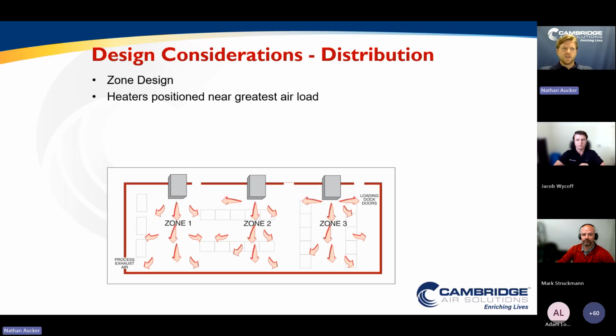So we're looking at design considerations in distribution. You really want to break down the facility into zones, if at all possible, especially in an open space, and try to manage expectations within each zone. Heaters really are best positioned, what we found, near the greatest air load. You can see here we've got loading dock doors on the top end, and these units are positioned near those doors, where you may have infiltration as they're opened and shut throughout the day as the facility moves equipment around. That high velocity really gets you incredible distribution from floor to ceiling and all throughout the space.